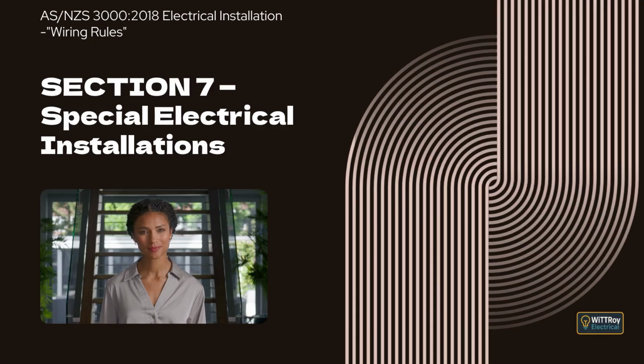Clause 7.3.8.1.2 Switching. This clause explains that the changeover device for an alternative supply must be selected to maintain the function of, and prevent damage to, the electrical installation. It explains that this includes maintaining continuity of the neutral conductor, correct operation of RCDs, and continued uninterrupted power supplies. It explains that the changeover device must open all active conductors of the normal supply when the alternative supply is connected, and that automatic switching must be clearly marked. It also explains that switching arrangements complying with AS/NZS 3010 are acceptable.